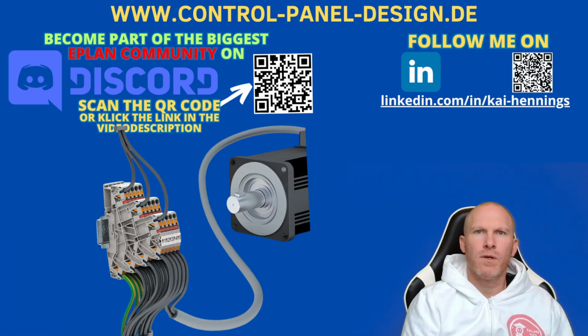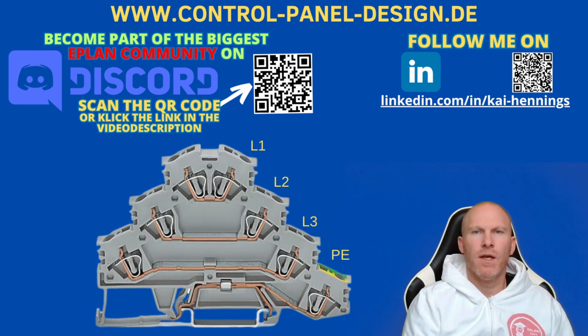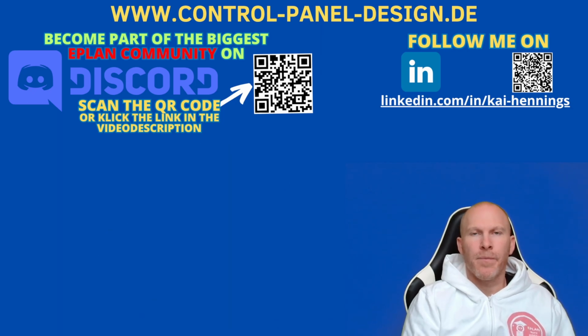The motor terminal block is a very special terminal where you can connect a motor directly on one terminal. The terminal consists of four levels, three for the three phases L1, L2, L3, and the fourth level for the PE. The PE is directly connected to the DIN rail so that you don't need to wire this on the internal side. There's also no connection on the internal side. And how to handle this is part of this video.